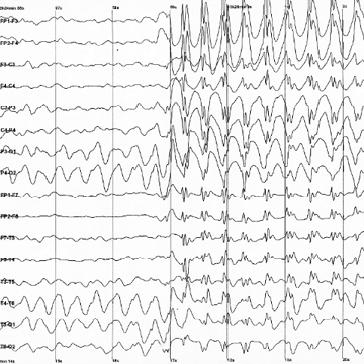Each electrode is connected to one input of a differential amplifier, one amplifier per pair of electrodes. A common system reference electrode is connected to the other input of each differential amplifier. These amplifiers amplify the voltage between the active electrode and the reference, typically 1,000 to 100,000 times, or 60 to 100 decibels of voltage gain. In analog EEG, the signal is then filtered, and the EEG signal is output as the deflection of pens as paper passes underneath.